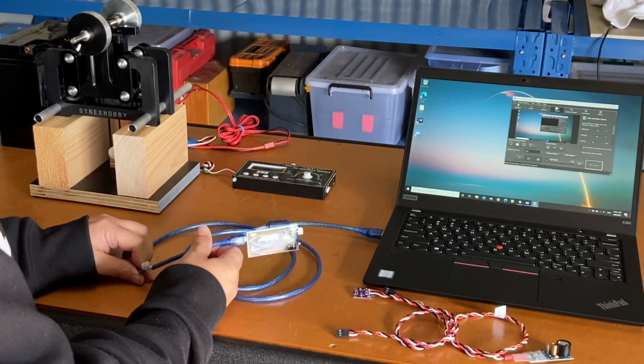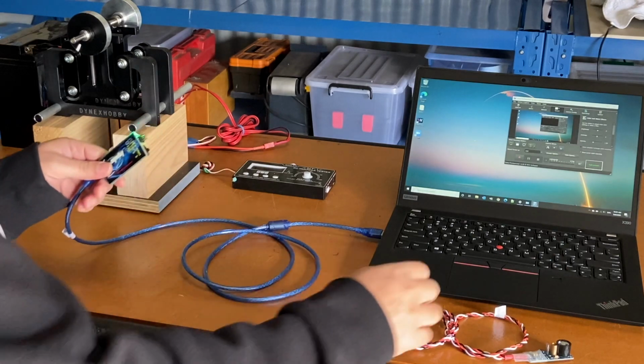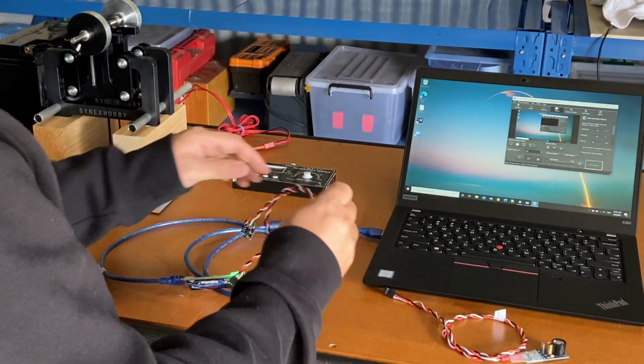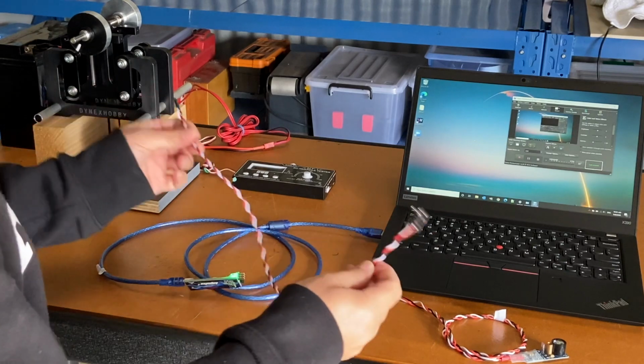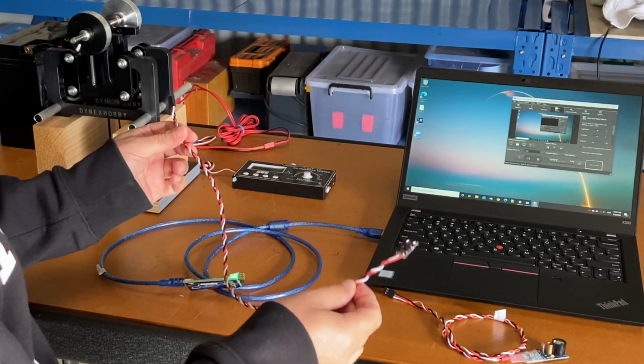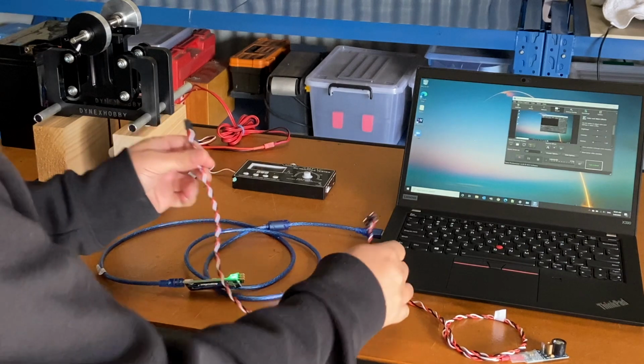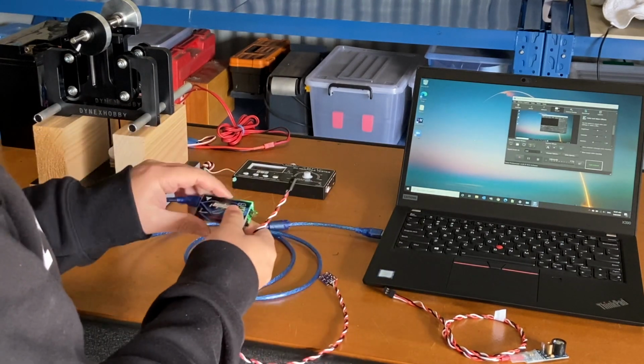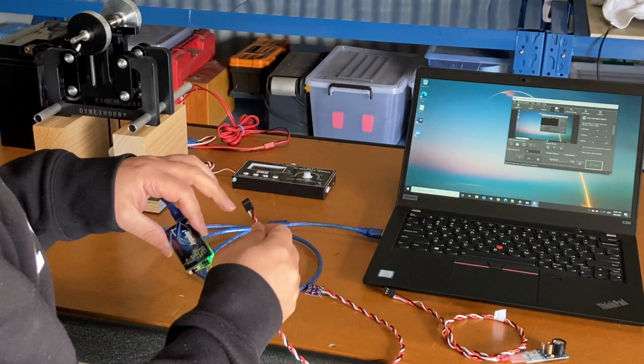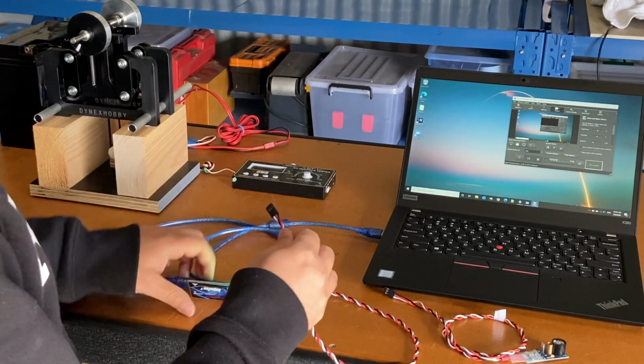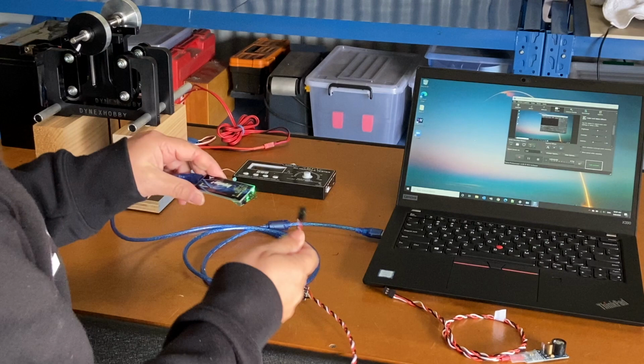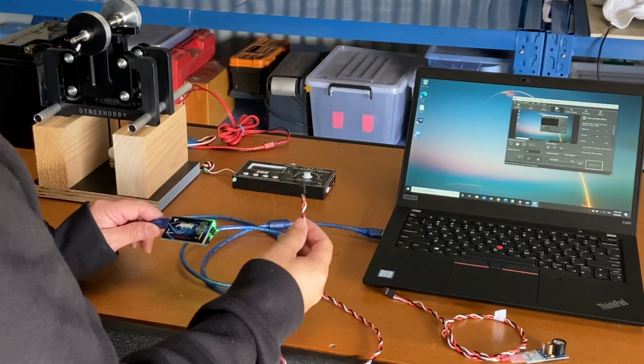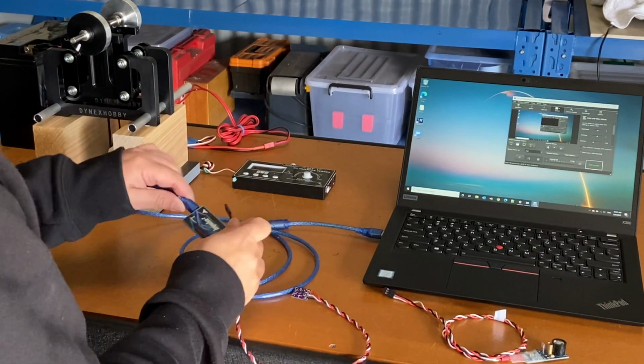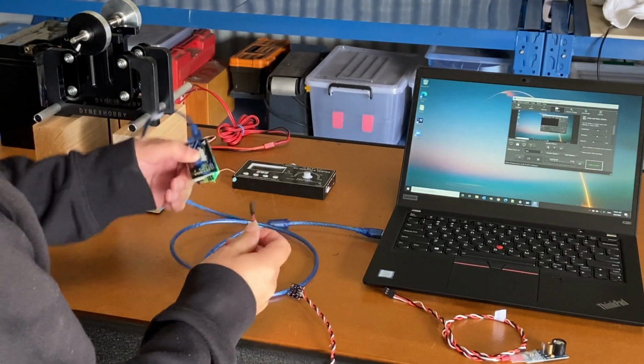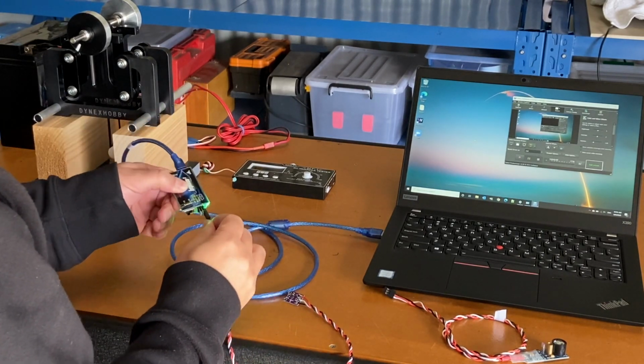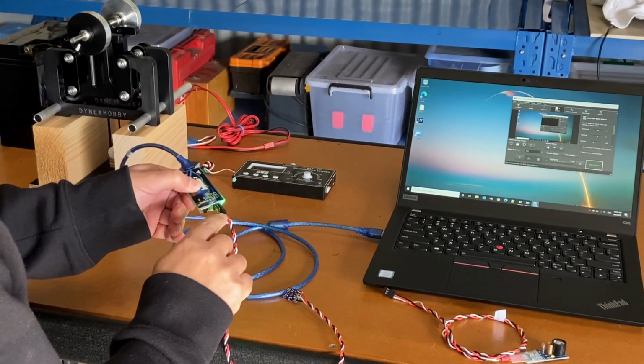So once that is all connected and set up in Windows, next thing would be to connect the sensors. So the standard accelerometer that comes with the kit is this accelerometer here. And the way it's connected is that the black wire faces the top label on the Impulse. So if I was to connect this to the Impulse, to the accelerometer port number one, I would plug that in like so, so that the black wire faces the top label.